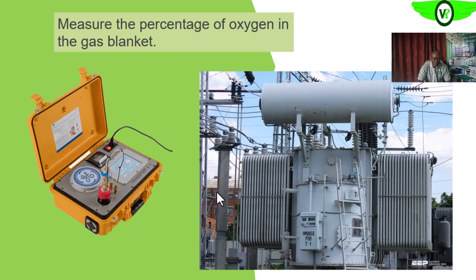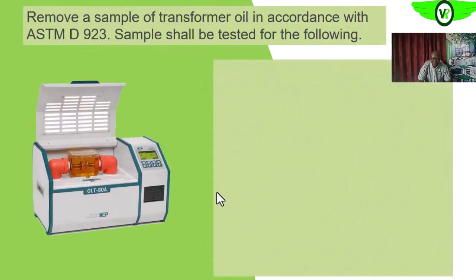So the percentage of oxygen in the blanket gas, we also want to test it if we have a blanket gas in the transformer. The reason for this is that there is a level of oxygen concentration that can cause the ignition of your transformer oil. So the percentage of oxygen, we want to maintain it at the most minimal level as much as possible.